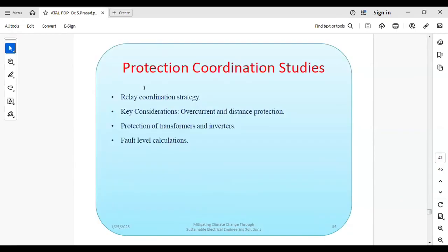And then the last one is protection coordination studies, as I said. Protection coordination studies is nothing but you have to set the relays in a PV plant. The relay or circuit breaker has to be coordinated, and the sequence of operation will be there. Okay, so that set time has to be coordinated for reliable operation of the PV plant during a fault situation.